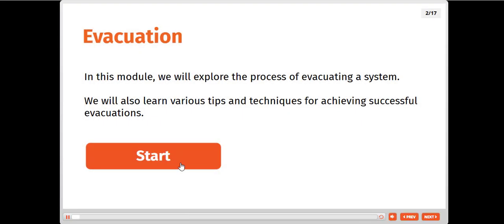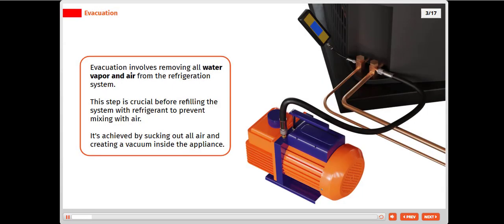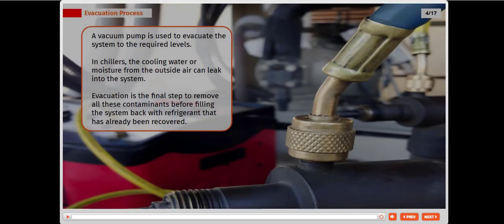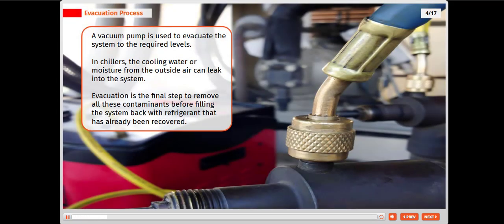In this module, we will explore the process of evacuating the system. We will also learn various tips and techniques for achieving successful evacuations. Evacuation involves removing all water vapor and air from the refrigeration system. This step is crucial before refilling the system with refrigerant to prevent mixing with air. It's achieved by sucking out all air and creating a vacuum inside the appliance. A vacuum pump is used to evacuate the system to the required levels.